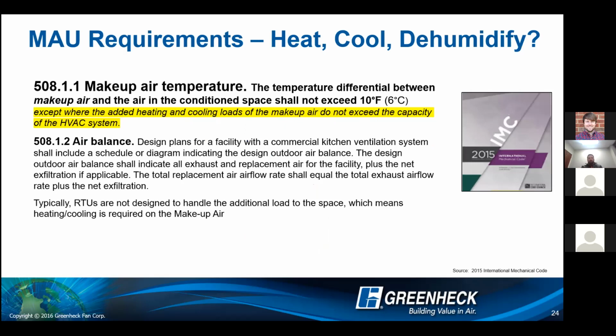So first, we're going to really quickly touch on 508.1.1, which is the ultimate question. Do I heat? Do I cool? Do I dehumidify? What in the world do I do with this air? And to be honest with you, I didn't really understand until years ago why this is even a question. The first line here says that the temperature differential between makeup air and air in the conditioned space shall not exceed 10 degrees Fahrenheit. Well, I can tell you that when it's 85, 90 degrees here in Wisconsin or Minnesota, that air was coming in at 90 degrees. Like, what the heck's going on here? That's outside of 10 degrees.